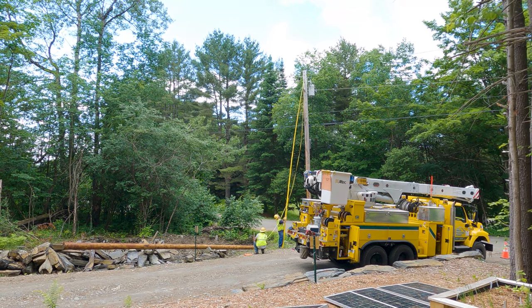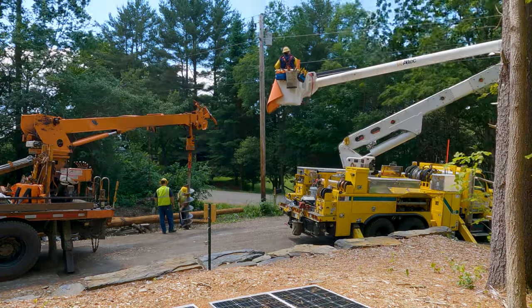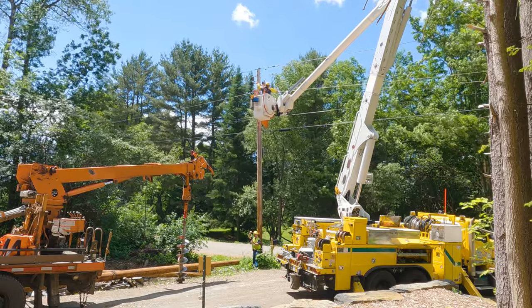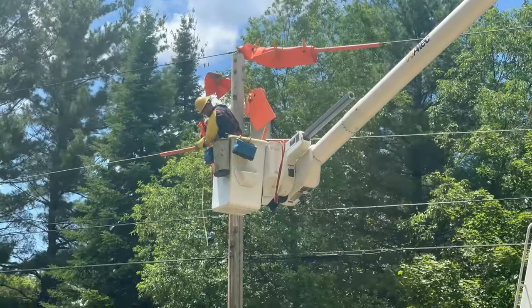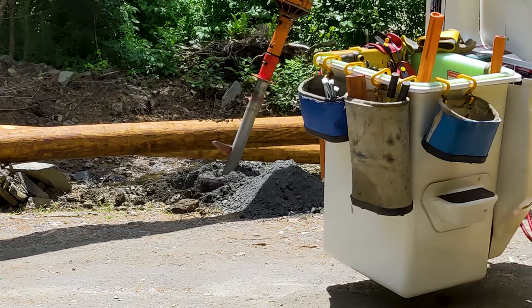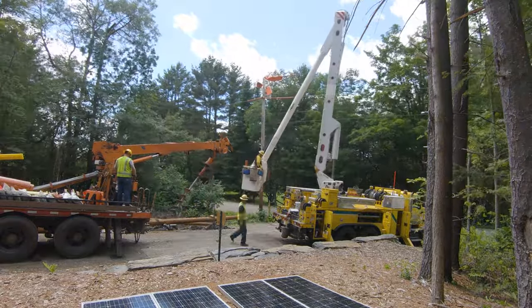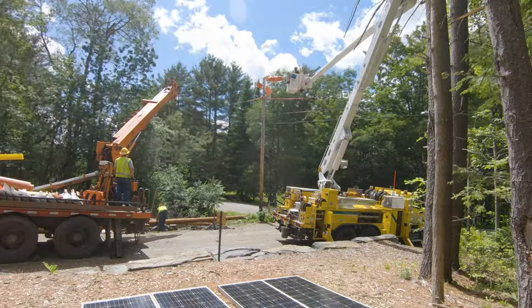After lunch they started working at the road. This is pole number zero — the main transmission line we're going to connect our sideline into. They had to install a push pole. Normally a pole has wires coming in one side and going out the other, so it's pulled equally in both directions. In our case we're installing a wire at 90 degrees to the main transmission line, and although there's another wire going off to a neighboring property on the other side, that's just a short drop with no real tension. Our new line would put a lot of tension on that pole, pulling it sideways.